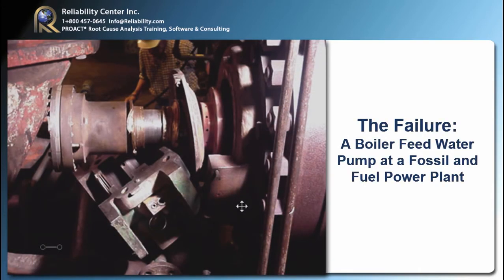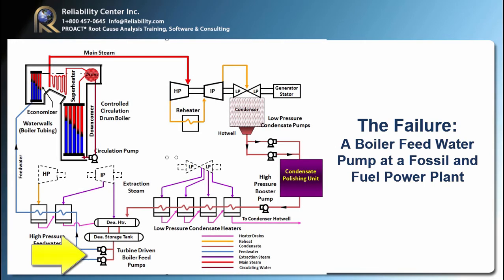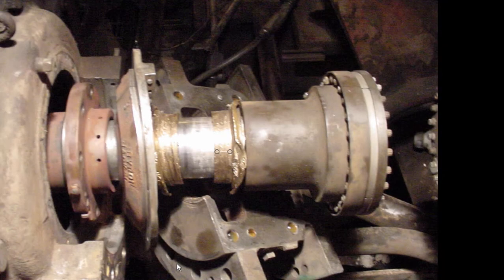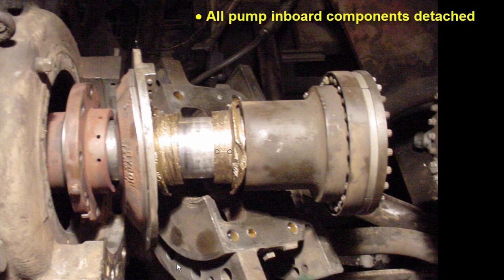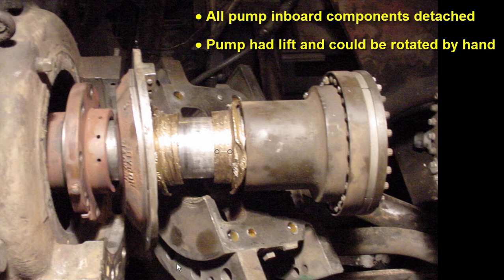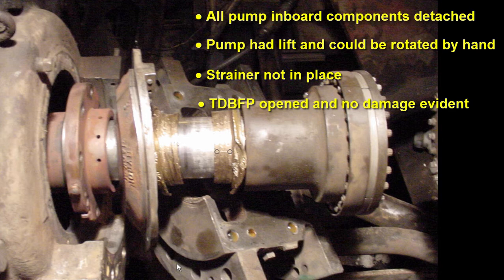The failure occurred on a boiler feed water pump at a fossil fuel power plant in the northeast section of the United States. The pump in question is this outboard boiler feed pump. The plant was operating normally and this pump shut down during operation, of course tripping the plant. Looking into the pump, we found that all the pump inboard components had become detached. The pump had lift and could be rotated by hand. The strainer was not in place, and when the turbine-driven boiler feed pump was opened up, there was no damage to the impeller and no damage to the housing.